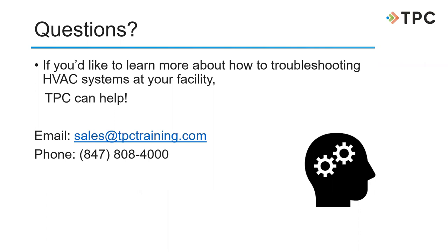We got an attendee with a question about the issue of ice. If we see ice on a discharge line, is that a restriction of a TXV valve? And I'm wondering if there is a possibility of finding ice on a discharge line. Ice on a discharge line, you've got a lot of liquid going to your compressor then, if that's the case. Because normally the side coming in on the suction line would be the ice. If the suction line is iced up, yes, that would be from the compressor getting too much liquid back. But I've personally never seen a discharge line that was iced up before, Ryan.